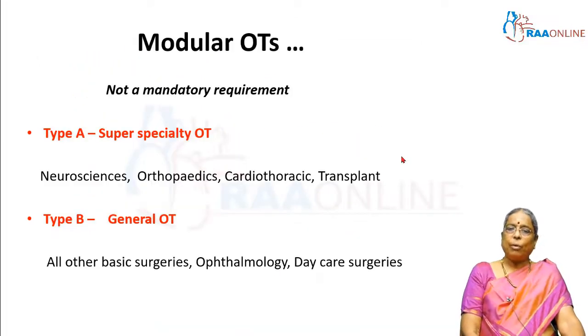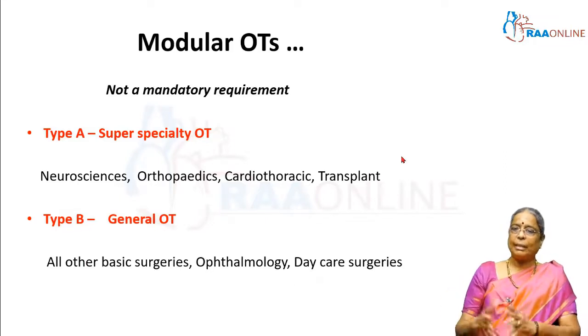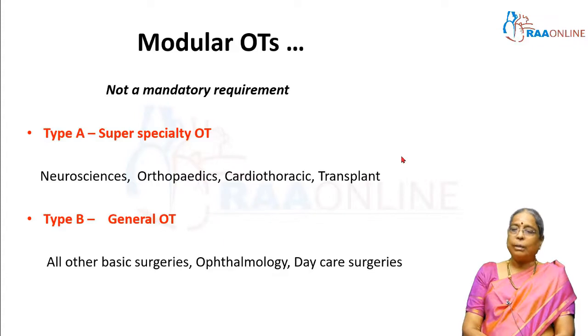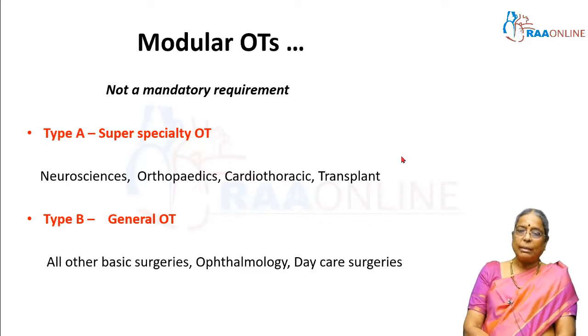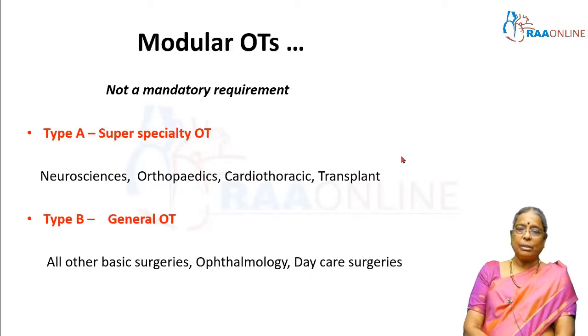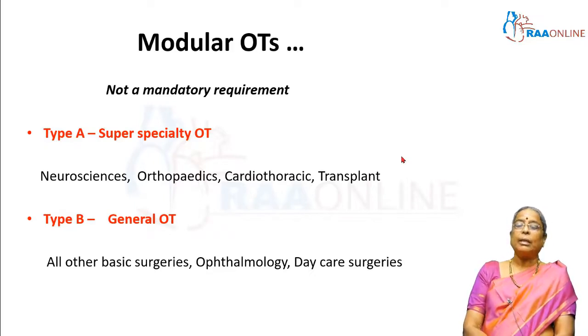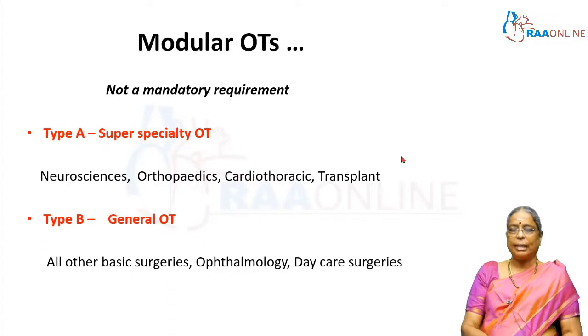Now, is there a requirement for modular OTs? Modular OTs are those OTs which are prefabricated and then brought in and fitted — just like we have modular kitchens, we have modular OTs too. But modular OTs are not a mandatory requirement. The OTs are divided into type A and type B. The type A OTs are the super-specialty OTs which require more stringent environmental conditions; these are the OTs where you perform neurosurgical procedures, orthopedics, cardiothoracic, and transplant procedures. The type B OTs are generally the general OTs where other basic surgeries are done — ophthalmic surgeries, daycare surgeries — with less stringent conditions than the type A OTs.